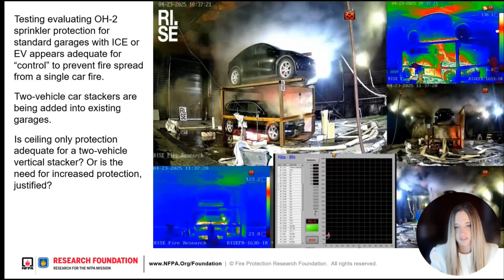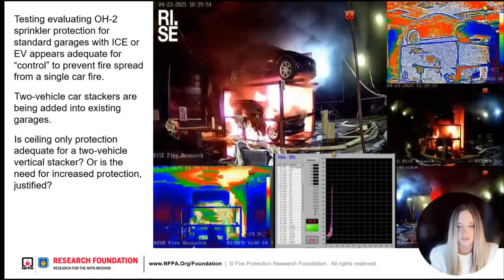So here, I'll let this video play. I'll note that this is below what NFPA standards currently require. Standards now require a higher water density delivered at the ceiling only, upping it a couple hazard classes, or requiring sprinklers at each level. So what we found was that the protection required for single vehicles in standard garages, which we tested at the single vehicle level, was not adequate.